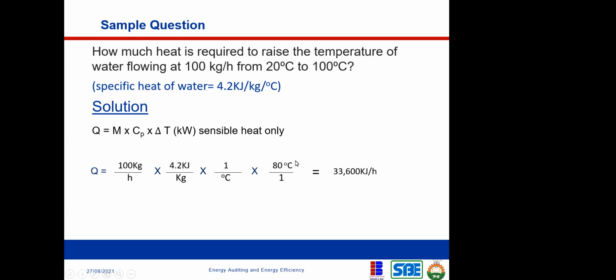This 80 is 100 minus 20, right? Maybe I should have written it 100 minus 20 so that it doesn't confuse anyone. We know what this temperature difference is. 100 minus 20, that is 80 degrees centigrade. So when you press your calculator on this, you're going to get 33,600 kilojoule per hour. That is quantity, that is the heat. Okay? That is the heat that is transferred.